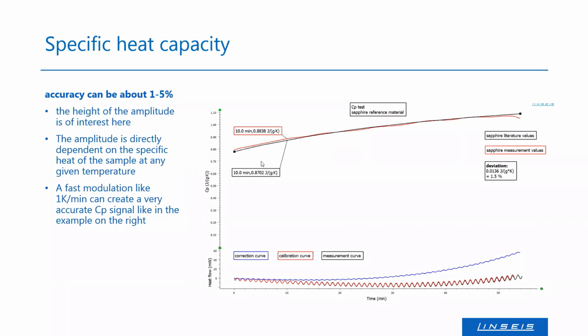And so with the chip DSC, or through the temperature modulation, we could get an accuracy of roundabout 1 to 5% error here. So that's a good thing for a DSC. If you remember, we are measuring around 25 or 20 milligrams of our sample here. And what we also can see is the amplitude is directly dependent on the specific heat here. But maybe we've got another example where I can explain this.